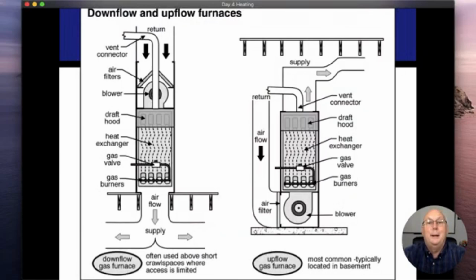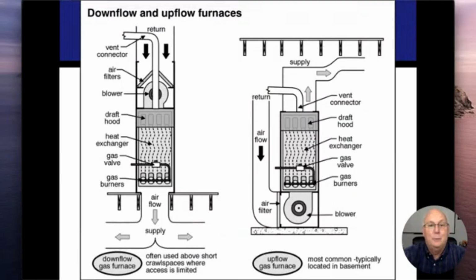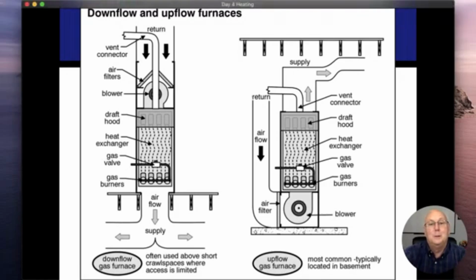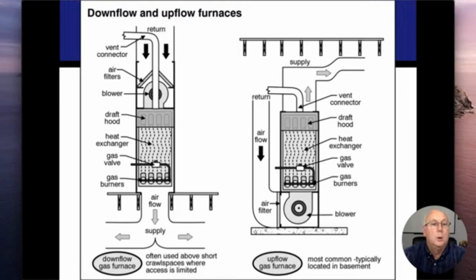All right, going back to my airflow. It doesn't matter if it's upflow, downflow, or horizontal, I don't care. The order of flow is always going to be the same: filter, fan, heat exchanger, and then at the top on the right picture is where my air conditioning coil would go if it was there. On the left picture, downflow furnace: filter, blower fan, heat exchanger, and if I had an air conditioning coil, it would be down at the bottom underneath the heat exchanger.